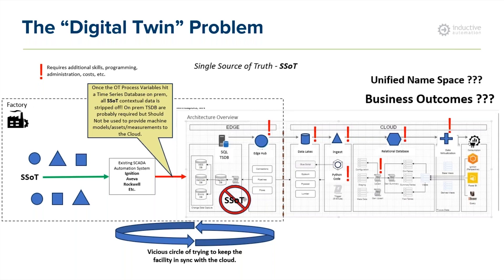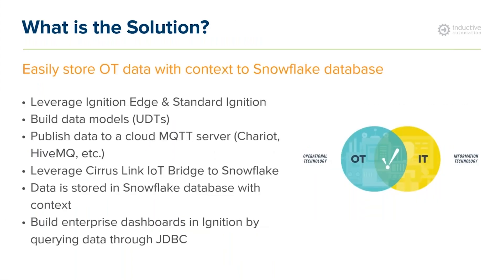We have to approach it differently, and that's the solution we want to share today. The solution leverages Ignition and Cirrus Link to move data into a Snowflake database that allows you to store OT data with context — all delivered at the edge as a single source of truth. It leverages Ignition or Ignition Edge to connect to all devices, build data models or UDTs providing asset information and metadata, and publish that data to a cloud MQTT server using MQTT transmission and the Sparkplug specification. Then we use a Cirrus Link IoT bridge for Snowflake to move that contextualized data to Snowflake automatically, with tables and structures already built out automatically.